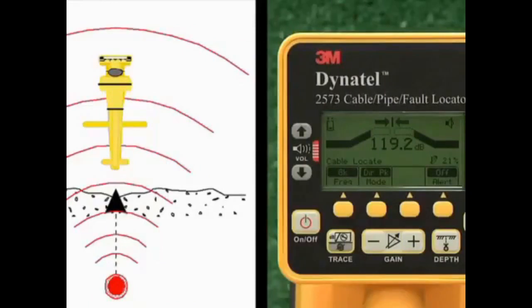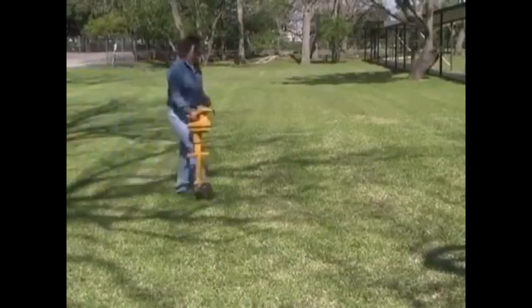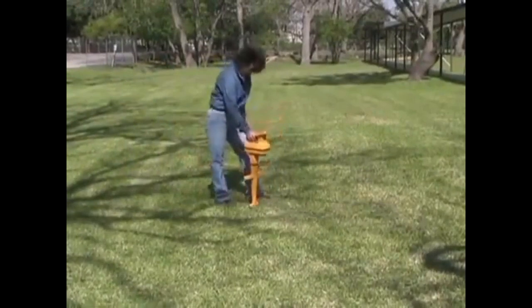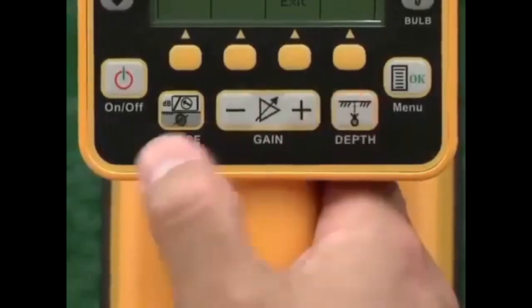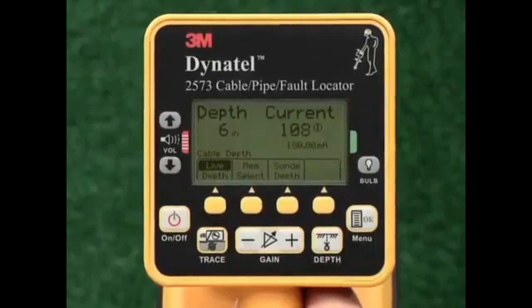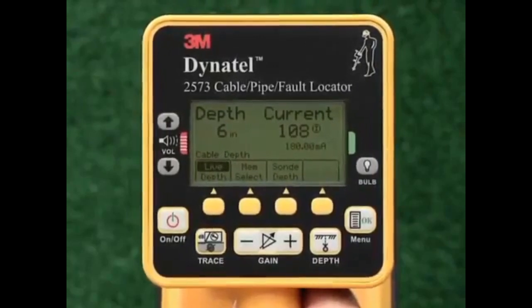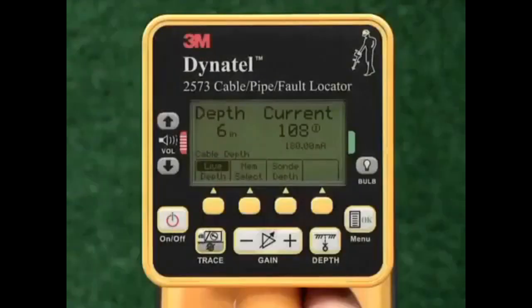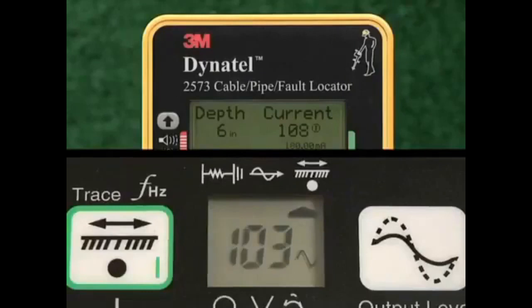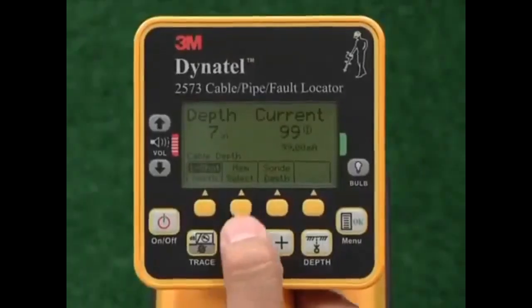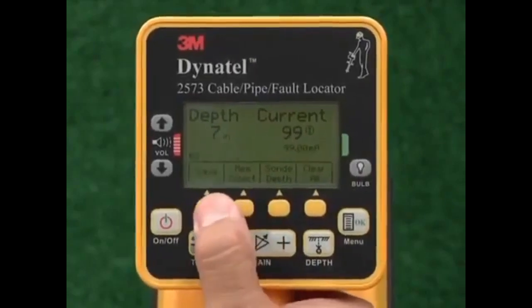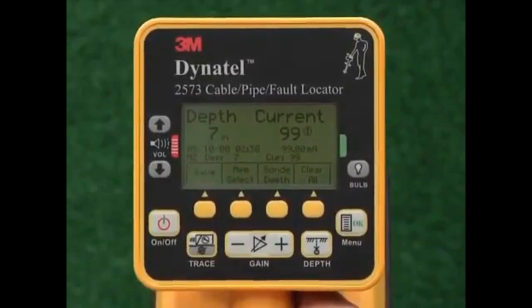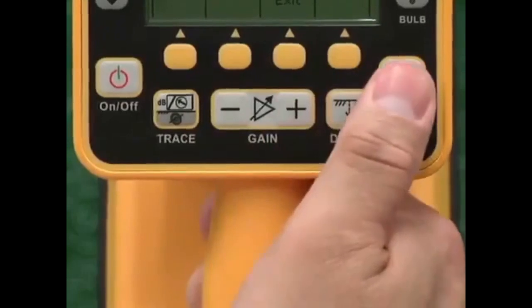See Advanced Application Techniques for information about measuring the symmetry of a locate signal. To verify the target path, measure the depth to the conductor. Place the tip of the receiver on the ground and press the yellow command key labeled Depth. The depth of the conductor will appear on the left-hand side of the screen, and should match the value you are expecting for this particular utility. On the right-hand side, the relative current of the conductor will appear. If you are locating a single conductor using the direct connect method and are on target, this value should be very close to the relative current flashing on the transmitter. You can save this depth and current reading along with four others by pressing the save command key while in the depth screen. Press OK to return to the locate screen and continue marking the target path.